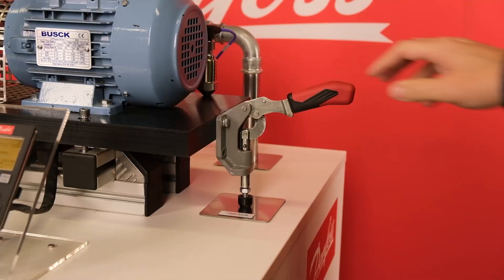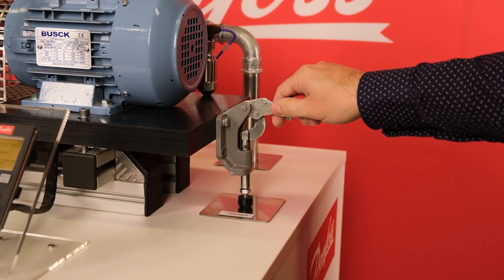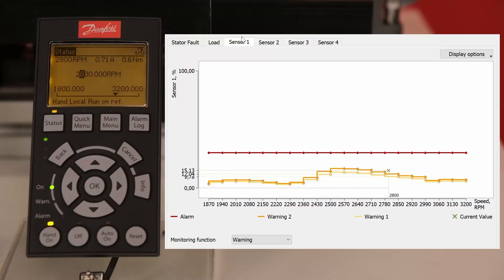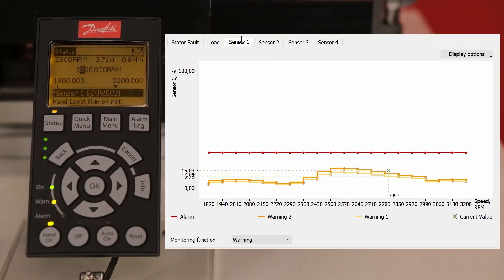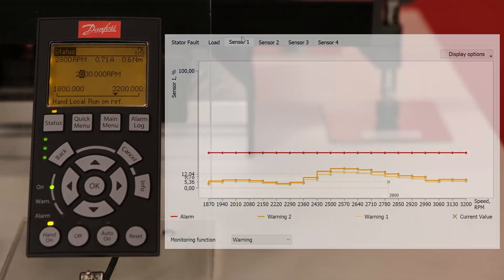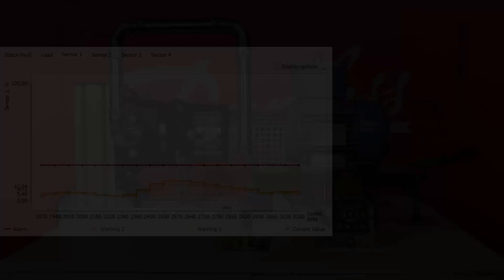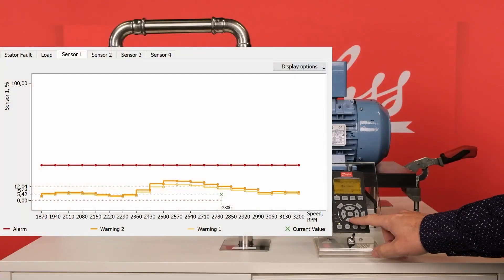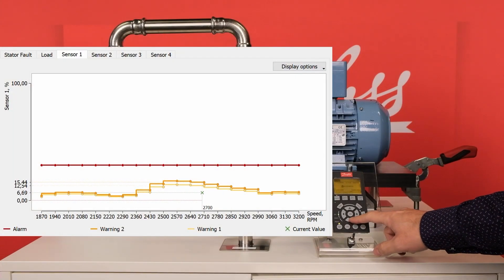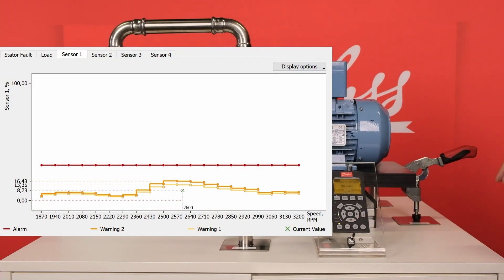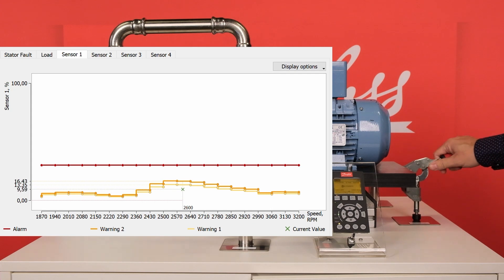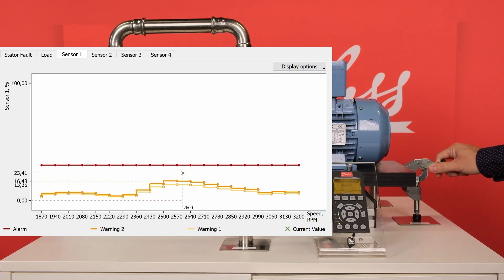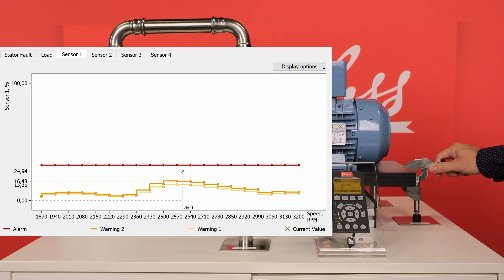For checking the vibration monitoring function, the handle is pushed down, creating a misalignment between the motor and the pump. This will increase the vibration level. Have you noticed the shape of the threshold curve? The explanation is that vibration depends on speed. The CBM function is unique because it correlates speed with the vibration level.